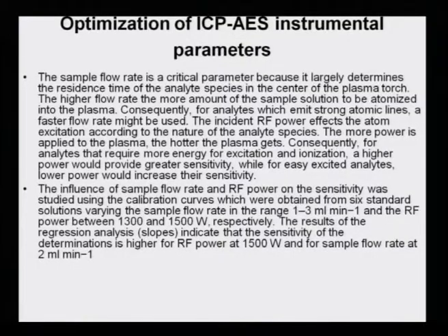Optimization of ICP-AES instrumental parameters. The sample flow rate is a critical parameter because it largely determines the residence time of the analyte species in the center of the plasma torch. The higher the flow rate, the more sample solution is nebulized into the plasma. Consequently, for analytes which emit strong atomic lines, a fast flow rate might be used.